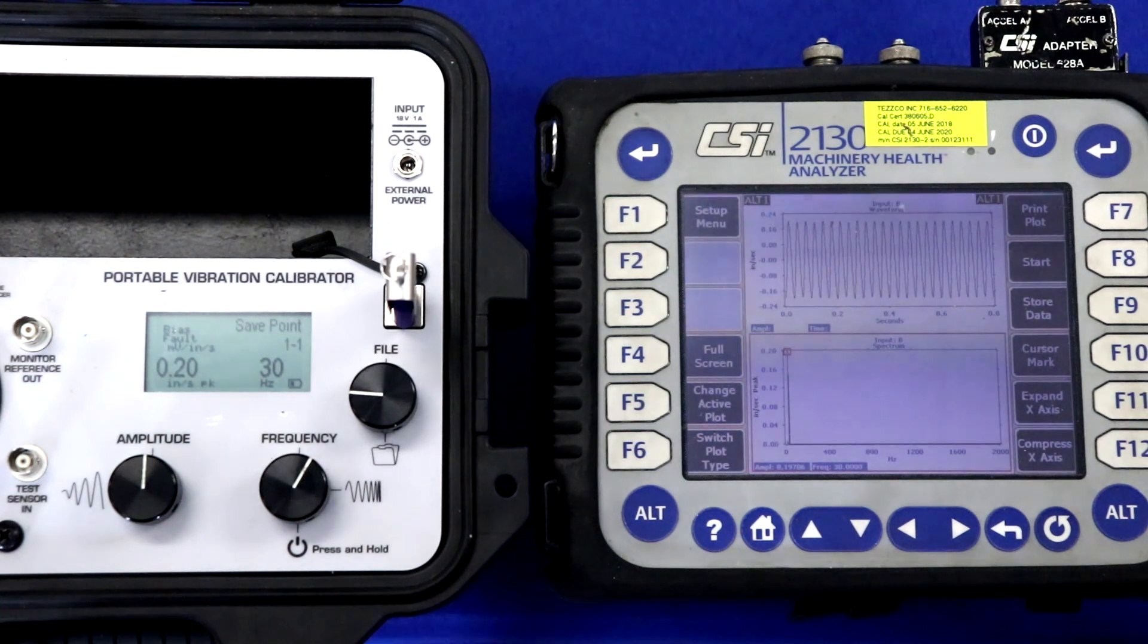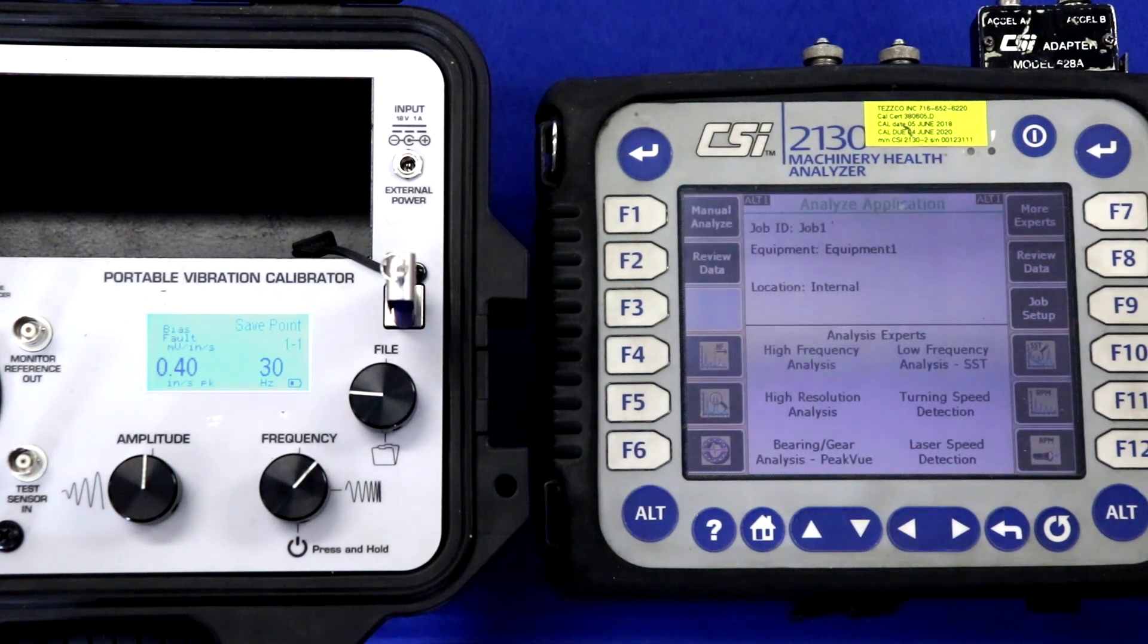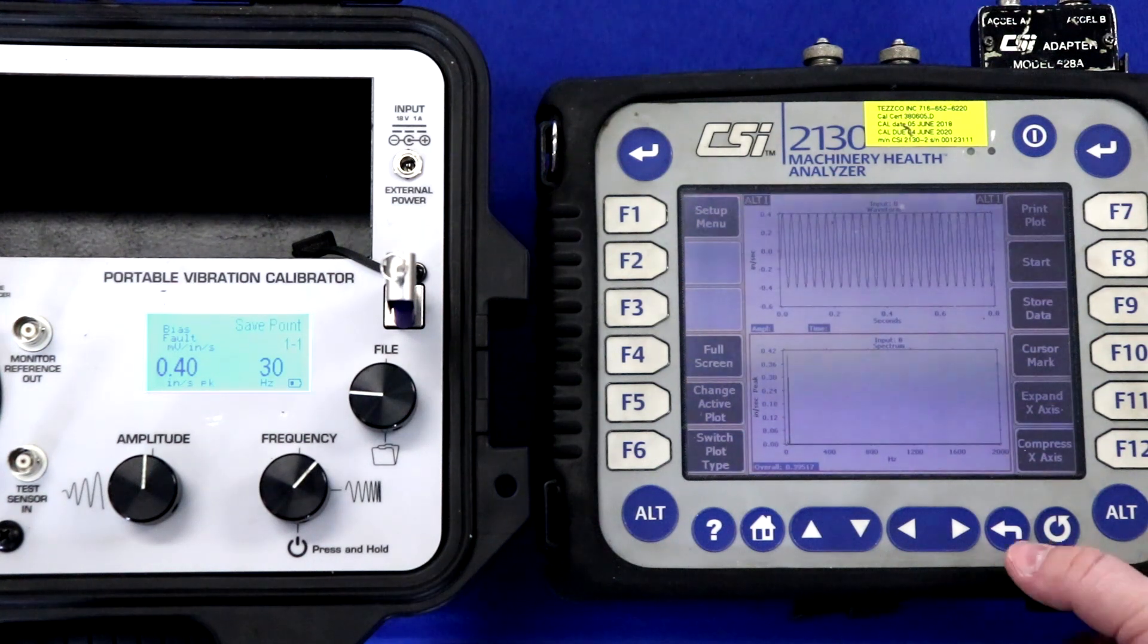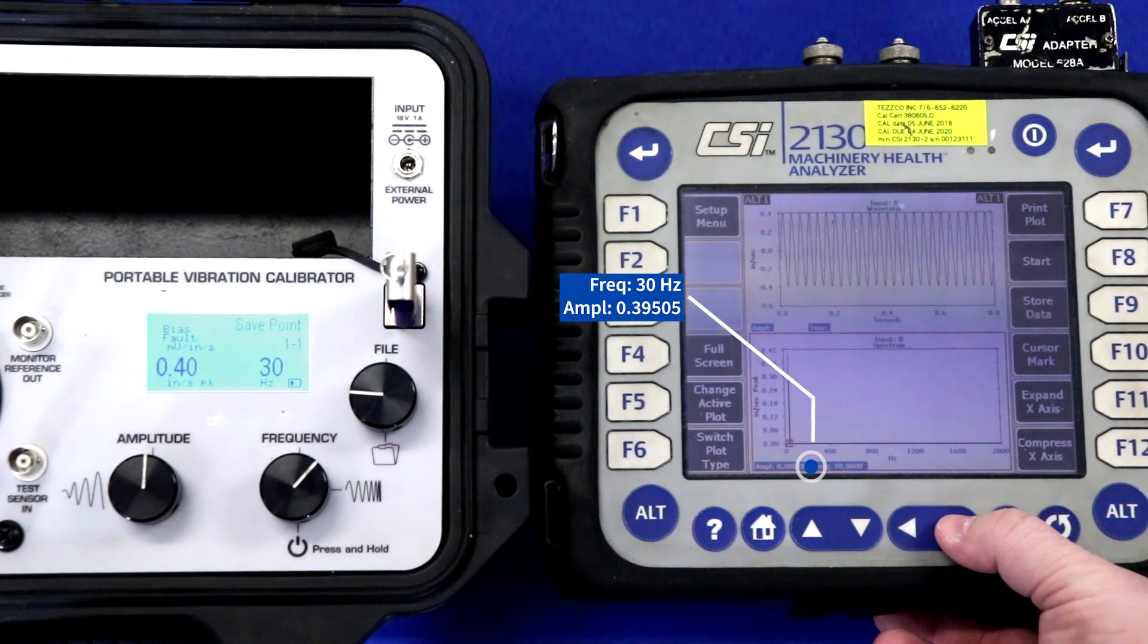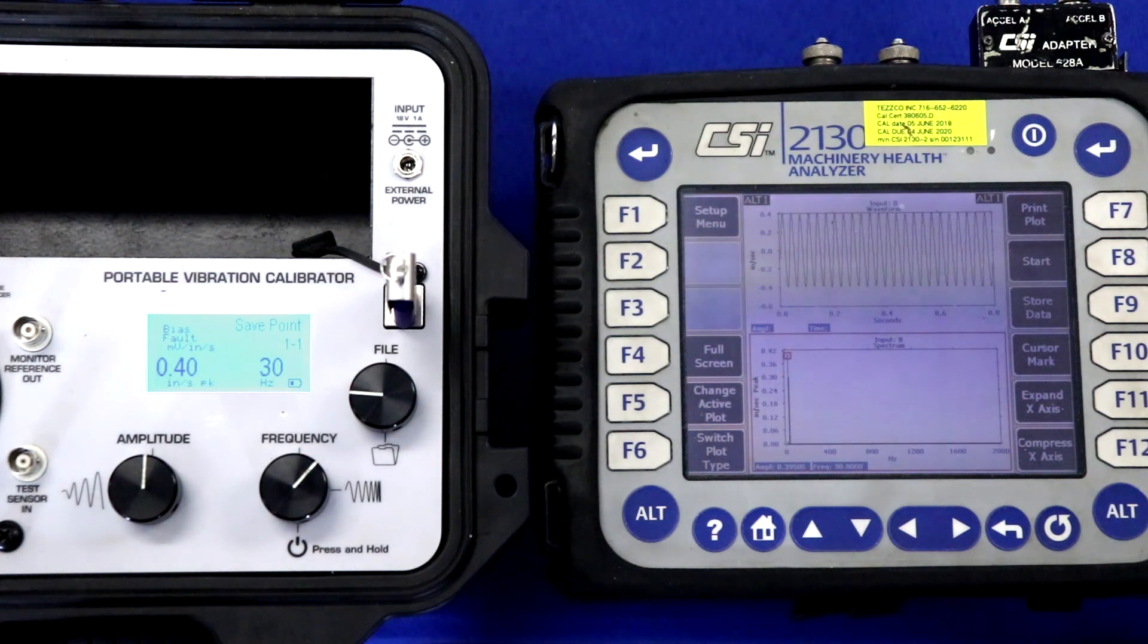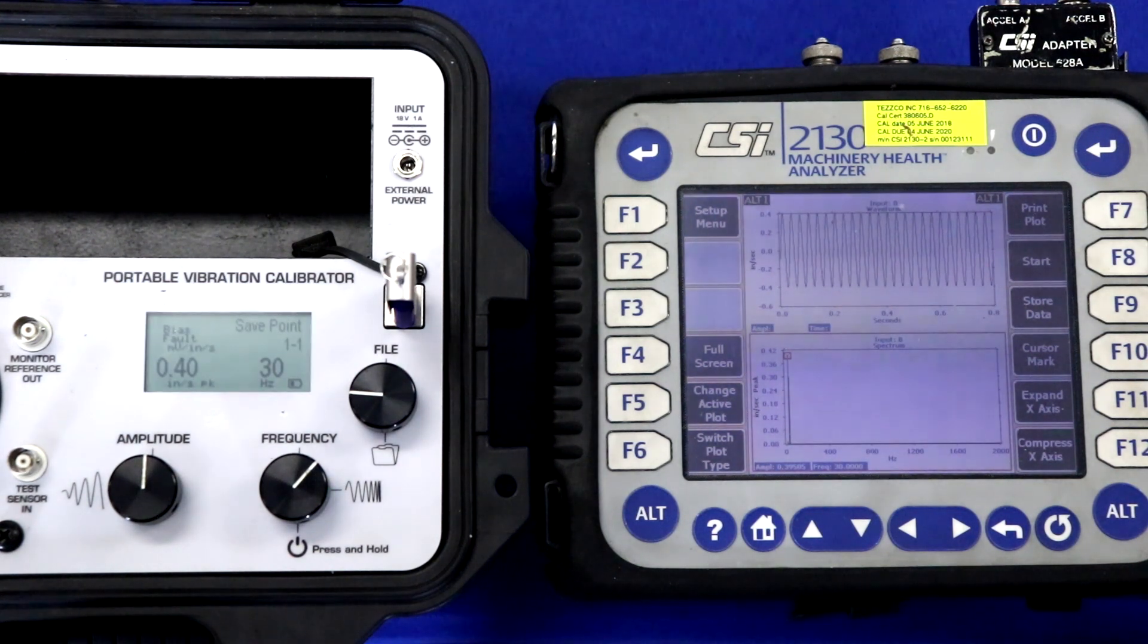We can now move on to 0.4 inches per second peak, and acquire our data again by pressing manual analyze and recording. We'll take our eight averages, and once again, our measurement turned out very close to the known value of 0.4. Our vibration is centered at 30 hertz at 0.395 inches per second peak. So again, very close, and you can see in the measurement that there's no distortion here.